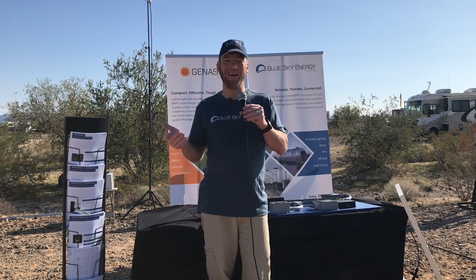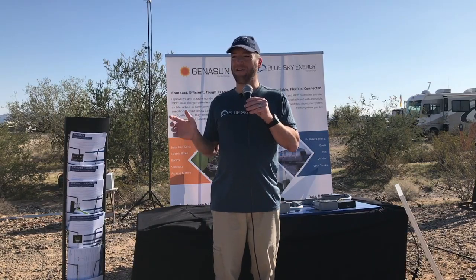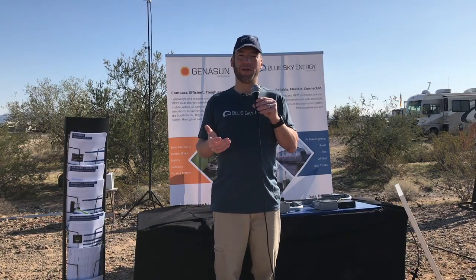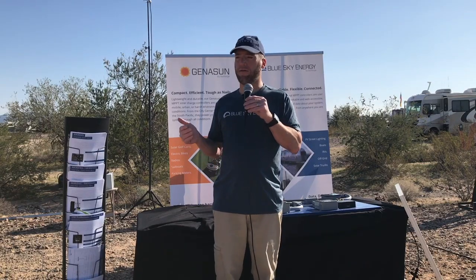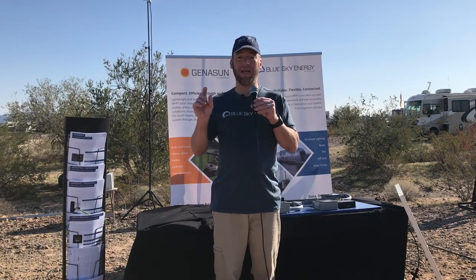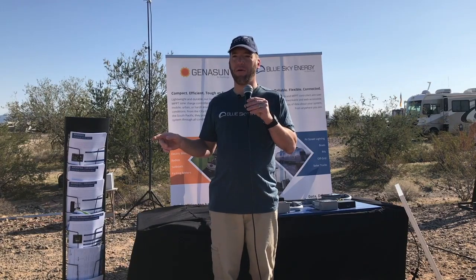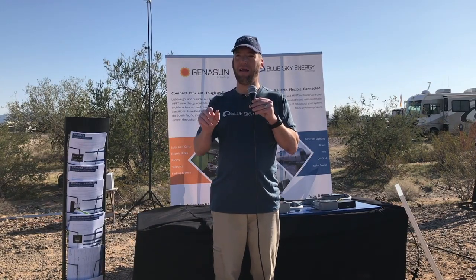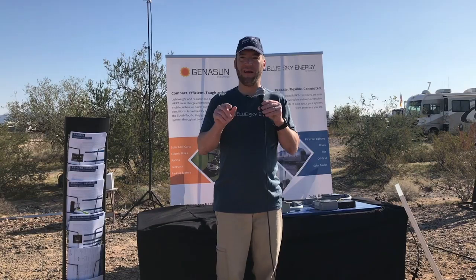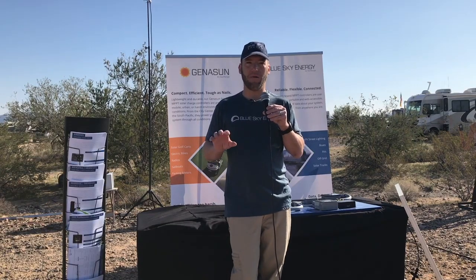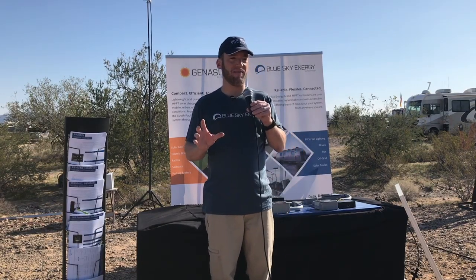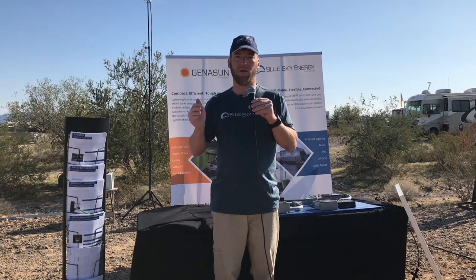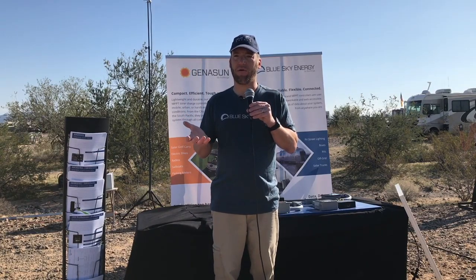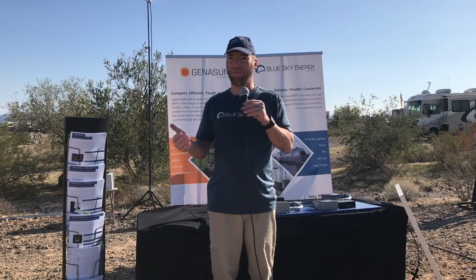It's like any charger you buy is not suitable, it's too much of an open-ended question. I think a lot of chargers are programmable. Some have set points, like an AGM setting, which might be suitable for a lithium battery even though it doesn't say lithium battery, but you'd have to look at what those settings are. A common AGM setting is going to have a low absorption voltage and a high float voltage in general, so you very easily could have an off-the-market charger which is compatible.